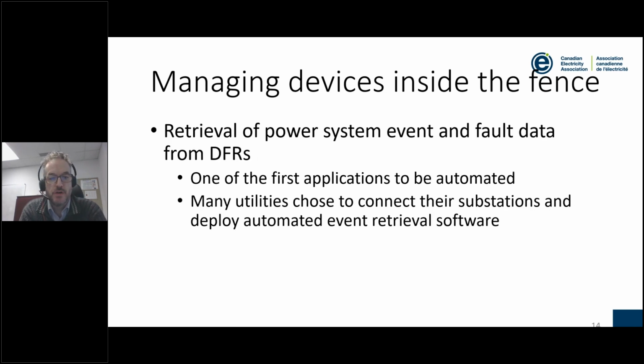One of the first applications where we really saw automation kick in was the ability to retrieve power system event and fault data from digital fault recorders: oscillography reports, sequence of events, any type of fault data. That's really one of the first applications to be fully automated.